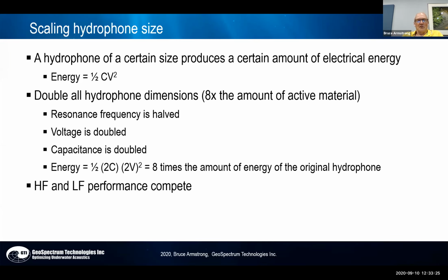And so you can see that the high frequency performance of a hydrophone and the low frequency performance compete with one another. If you want a hydrophone that works out to 200 kilohertz, you have to be willing to give up low frequency performance. You just can't get it. That high frequency hydrophone has to be small to operate at high frequencies. And when it's small, it doesn't harvest very much energy.